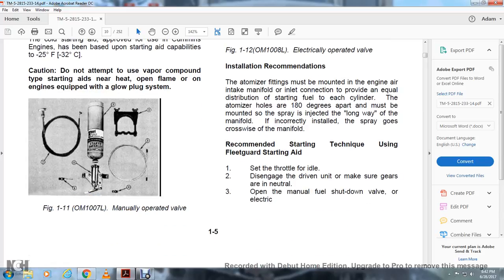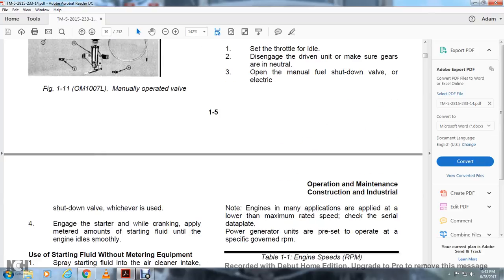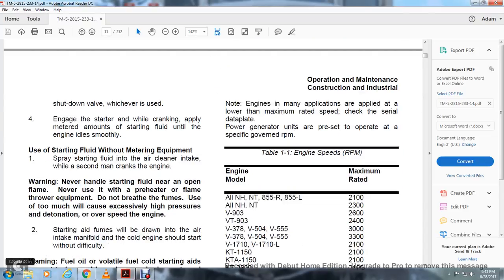Recommended starting technique: use the Fleetguard starting aid. Set the throttle to idle to disengage the driven unit. Make sure the gears are in neutral. Open the manual fuel shutdown valve or electric shutdown valve, whichever is used. While cranking the engine to start, apply a metered amount of the starting fluid until the engine idles smoothly.